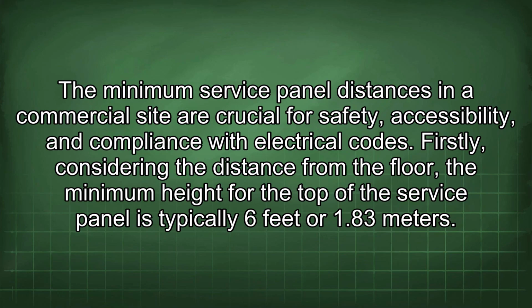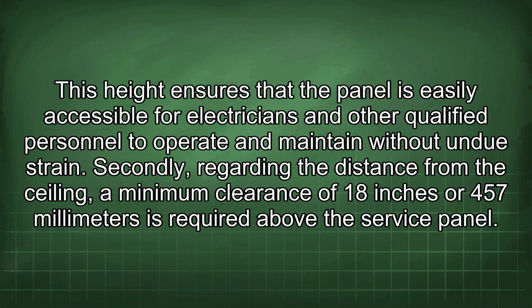The minimum service panel distances in a commercial site are crucial for safety, accessibility, and compliance with electrical codes. Firstly, considering the distance from the floor, the minimum height for the top of the service panel is typically 6 feet or 1.83 meters. This height ensures that the panel is easily accessible for electricians and other qualified personnel to operate and maintain without undue strain.